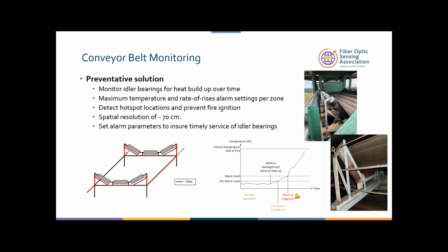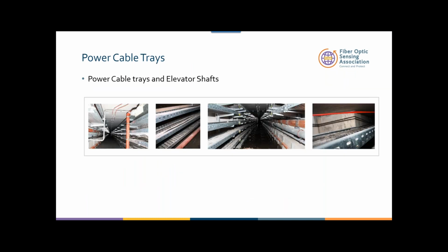The conventional one, as I talked about earlier, you either have a preset system that tells you the temperature or the rate of rise. But if you have any of them wrong, you are not doing what you're supposed to do, which is preventing a fire. You can have power cable trays monitoring as well. Here's an example of pictures where you can run the fiber optic cable within a cable tray, and you can tell the temperature of the cables, medium voltage, high voltage, you name it.